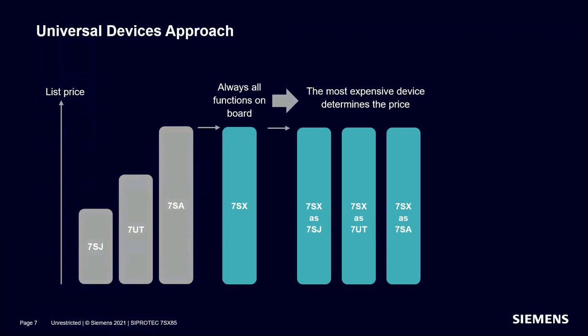The big disadvantage of this approach is easily seen, because the universal relay would have the same price for high-end applications like distance or transformer protection as for simple applications like overcurrent protection. As a consequence, always having all possible functions on board, the price of the universal relay would be determined by the most expensive device type.